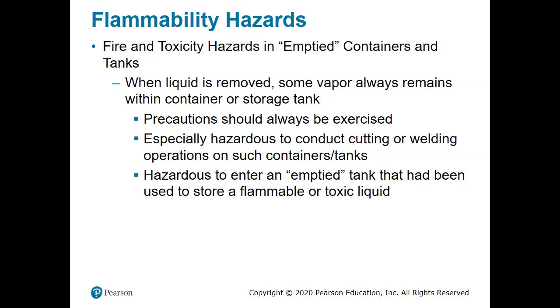And so regardless of what is in the container, we have to understand that that container, even when we empty it of all of its liquid, is still going to have some vapor-driven substance in it. So if the substance inside of the tank happened to be flammable, then we know that the vapor inside is also flammable. If the substance inside happened to be toxic, then we know that there is toxic vapor still inside of that tank. And so we have to be careful about its release. We have to be careful about its being discarded.